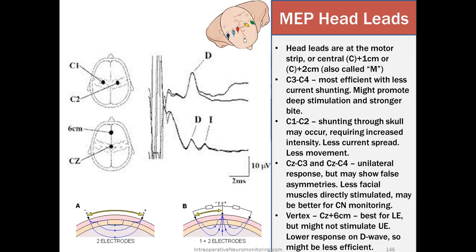So the first head lead placement also is C3C4, most efficient with less current shunting, might promote deep stimulation and stronger bites. C1C2 shunting through the skull may occur requiring increased intensity, less current spread, less movement. CZ to C3 and CZ to C4, a unilateral response but may show false asymmetries. Less facial muscle directly stimulated may be better for cranial nerve monitoring. And the vertex to the CZ plus 6 centimeters is best for lower extremities but might not stimulate upper extremities. Lower responses on D waves so might be less efficient.